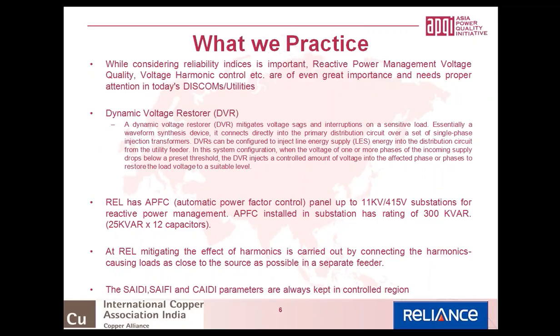What we practice, as I rightly said, there is a voltage harmonic which is generated by the high voltage load, and that creates various voltage sags and interruption. To take care of this, we have implemented an automatic power factor correction control module, which has a power capacitor bank of 12 capacitors, which are kept at each and every substation.